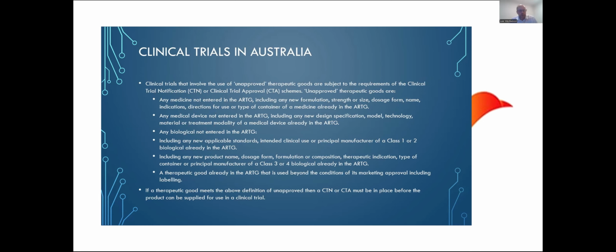Now, clinical trials in Australia. Every regulatory authority, every territory or country around the world, has its own requirements for clinical trials. Australia is no different. If you're going to use an unapproved therapeutic good, which is any one of the definitions in the bullet points, the one applicable to us is any medical device not entered in the ARTG, or even if it is on the ARTG but you've made some new design specifications or changes to the device that are not covered by your ARTG application or inclusion, it's considered an unapproved therapeutic good.